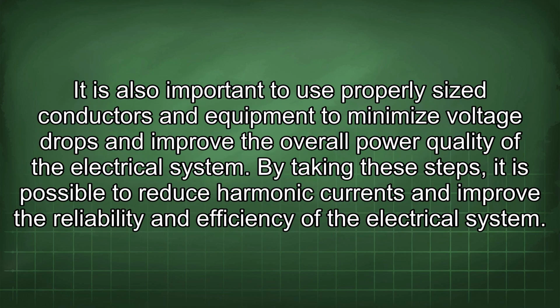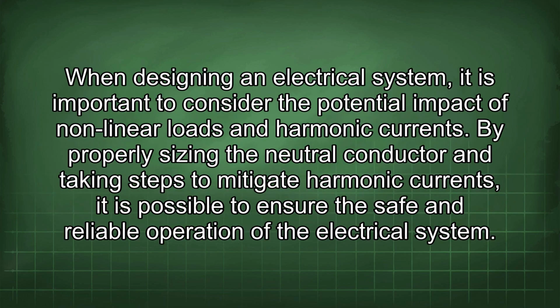It is also important to use properly sized conductors and equipment to minimize voltage drops and improve the overall power quality of the electrical system. By taking these steps, it is possible to reduce harmonic currents and improve the reliability and efficiency of the electrical system. When designing an electrical system, it is important to consider the potential impact of nonlinear loads and harmonic currents. By properly sizing the neutral conductor and taking steps to mitigate harmonic currents, it is possible to ensure the safe and reliable operation of the electrical system.